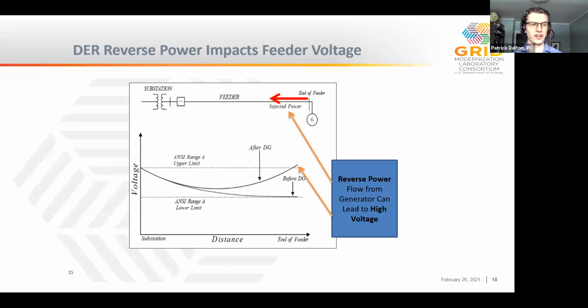But as we install DER on the system, this reverse flow can cause the voltage to rise near where that DER is located. It's really a function of that reverse power flow — the same effect that was causing the declining voltage in the previous scenario is now causing an elevated voltage near the DER.